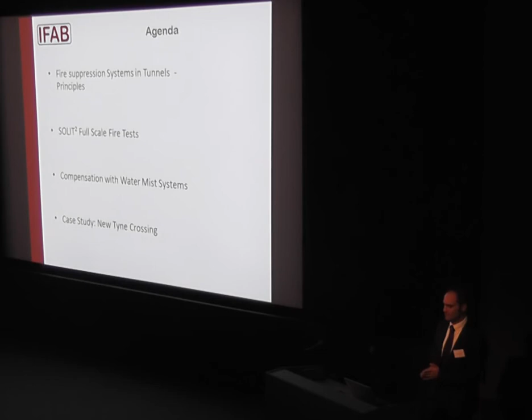First of all, fire development in tunnels. The problem is, when we look back 10 or 15 years ago, we learned a lot about fire development in tunnels - they can develop much faster than expected in the past. If you still look at guidelines, which are still valid and still the design basis in some cases, they say about 20 megawatts everything is fine, 30 megawatts everything is fine. The systems are designed for that, and you have many minutes, 20 minutes, before the fire brigade arrives, everything is fine. Yeah, we know today that in many cases that's unfortunately not the truth.